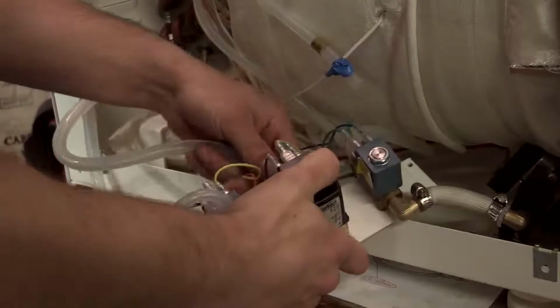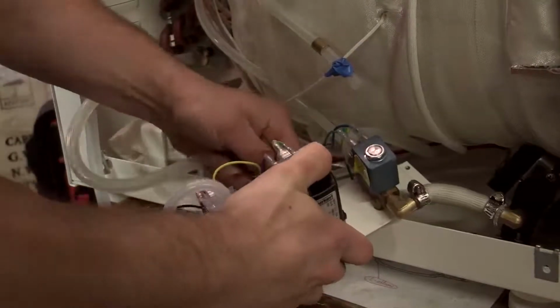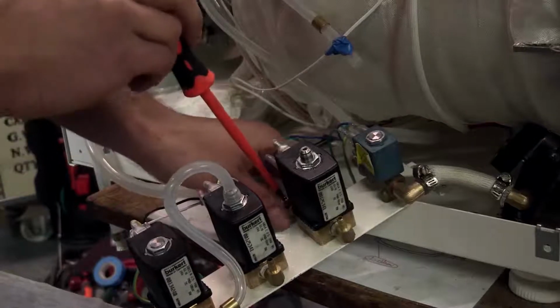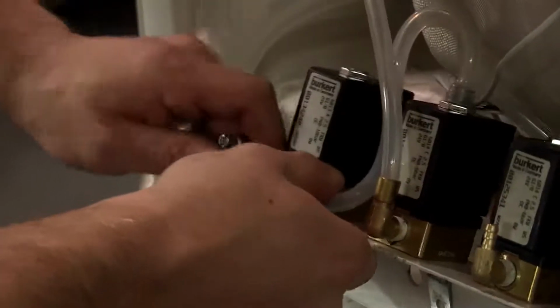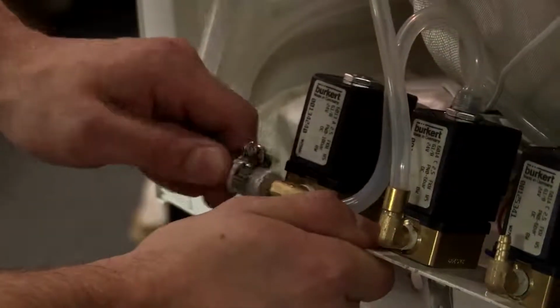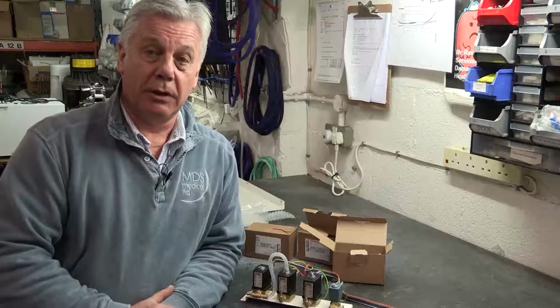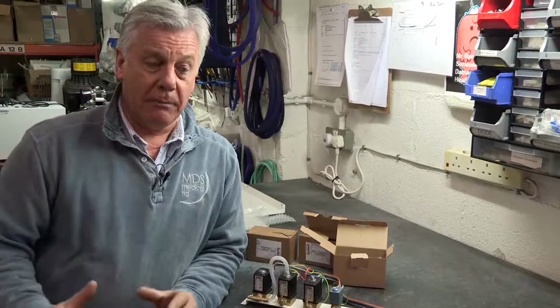We're finding that the duty that dentists use these machines, they could be running these machines at 15 times a day, 6 days a week. That's a lot of duty for a small valve to be working. They work like a piano. It'll open for a period of time and it will close for a period of time. So they're constantly in use through the cycle. A complete cycle will take about half an hour to 35 minutes, depending on the quantity of material that's been put into the vessel.